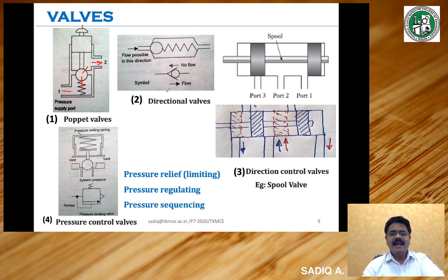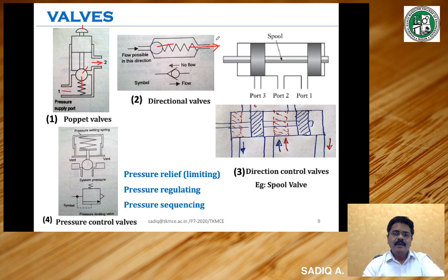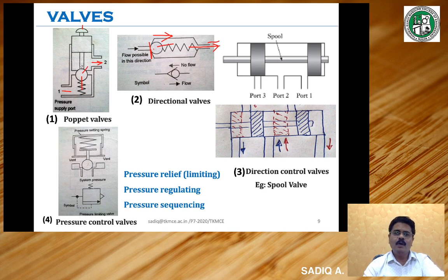Another kind of valve is the directional valve — it allows flow in only one direction. In its schematic, there is a ball that is spring loaded. When there is pressure from the inlet side, the ball is pushed so an opening is made and fluid flows through. But if flow comes from the reverse direction, it hits the ball and the passage is blocked. So flow is permitted only in one direction. In both poppet valves and directional valves, instead of a spherical ball, a disc or cone can also be used.